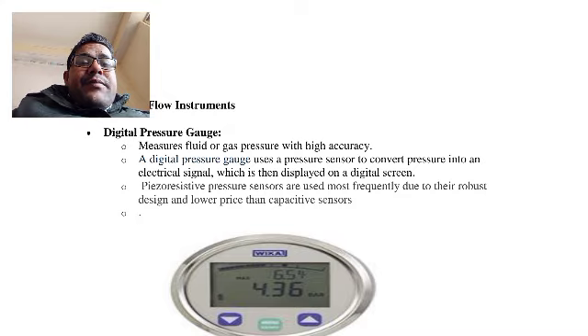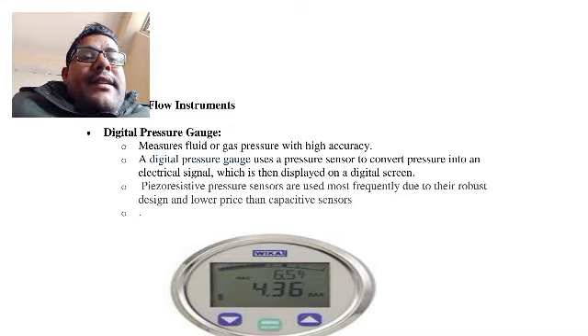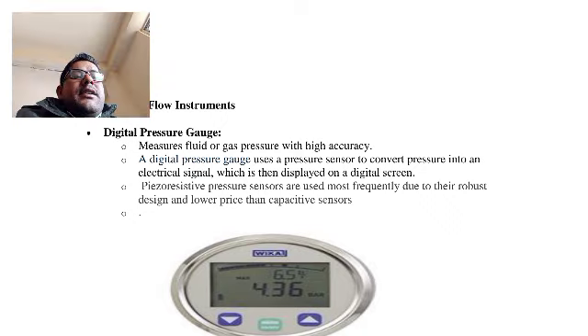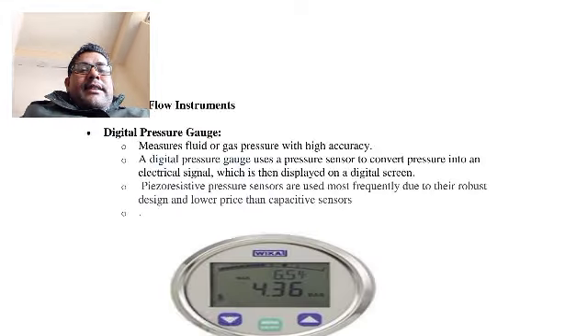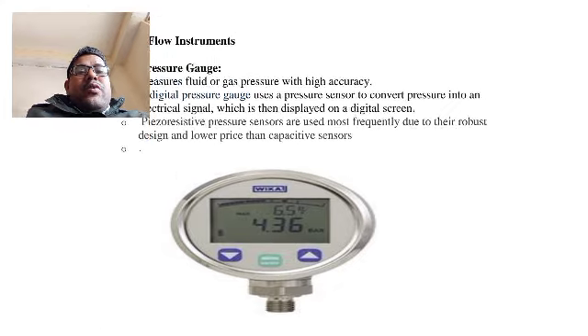So generally, the piezoresistive pressure sensor is used most frequently due to its robust design and lower price than the capacitive sensor. So digital pressure gauges we can design in two ways. First, we can use piezoresistive material, and second, we can use the capacitor. But piezoresistive material is generally used because of its low cost. Next we will discuss how it looks.